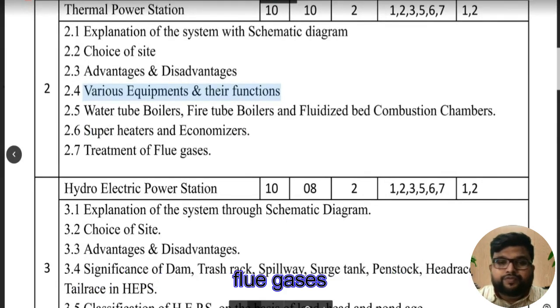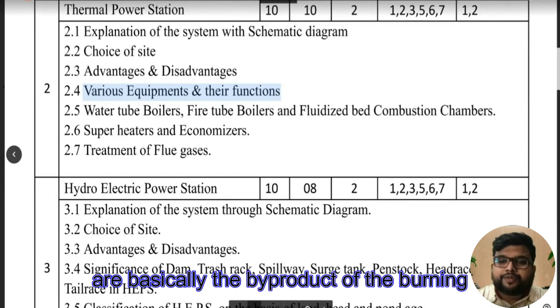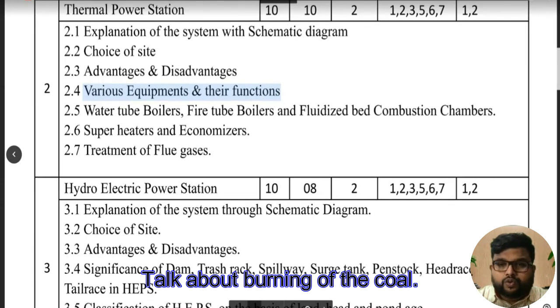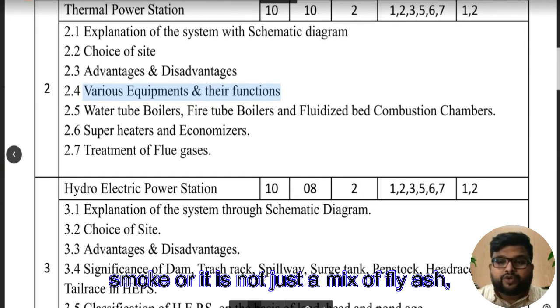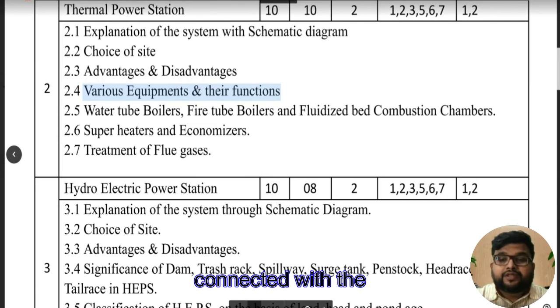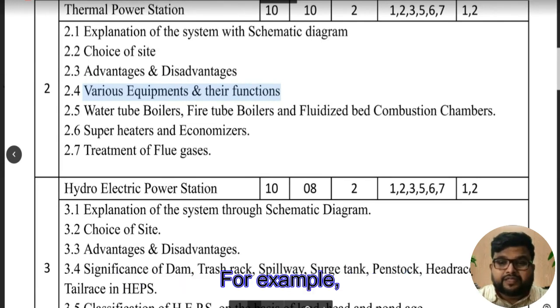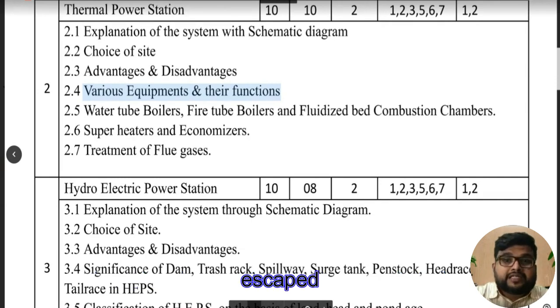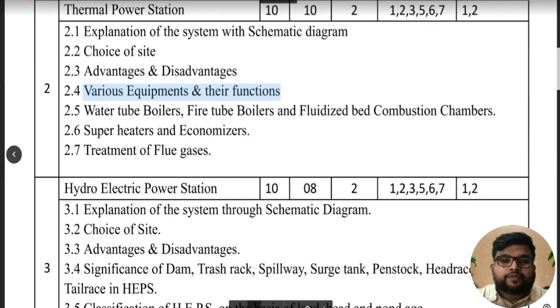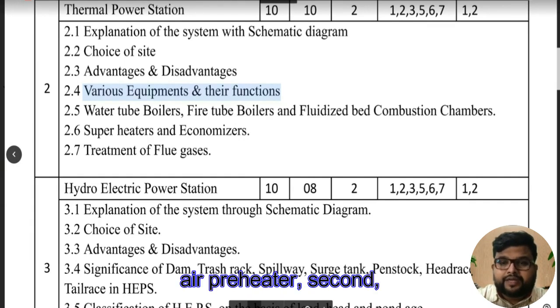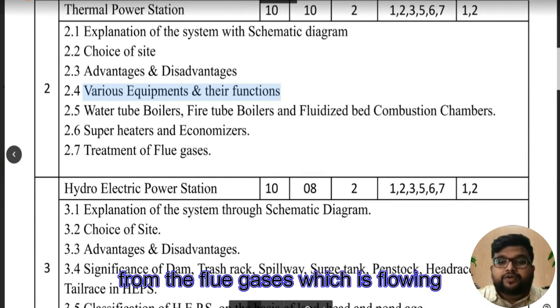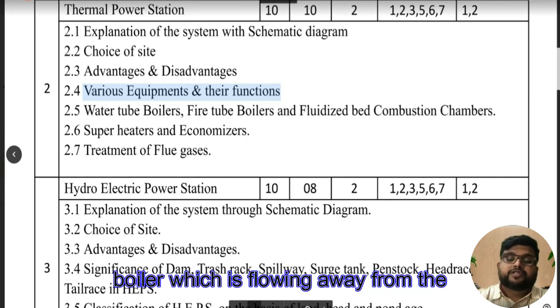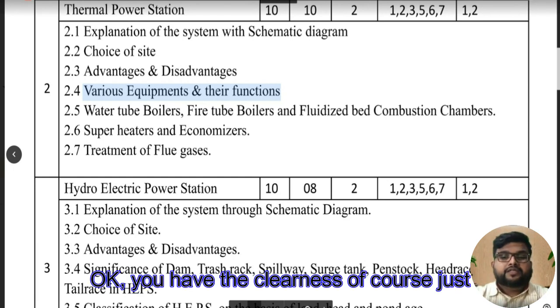Flue gases are basically the byproduct of the burning process — for example, burning of coal. Flue gas is not just a mix of smoke or fly ash; it is also connected with heat energy. A large amount of heat energy escapes through the chimney of the thermal power plant. Equipment like the air preheater and the economizer are basically extracting heat from the flue gases flowing away from the boiler.